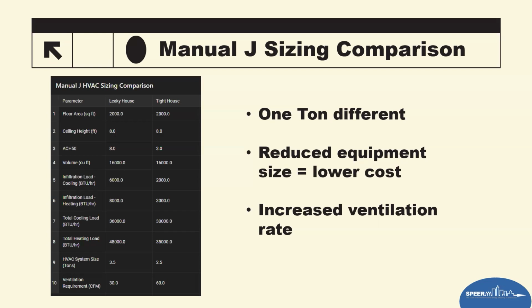And of course, it does also change the ventilation rate that's required. The code does address the fact that if you have a leakier house, you can use some of those levels of leakiness to offset what's required for mechanical ventilation. But that's not a good rule of thumb, to have it just leak profusely and then say that I don't have to do mechanical ventilation. But as you see at the bottom, a leaky house will only require 30, a tight house requires 60.